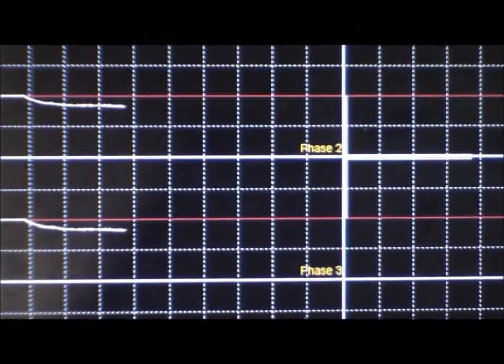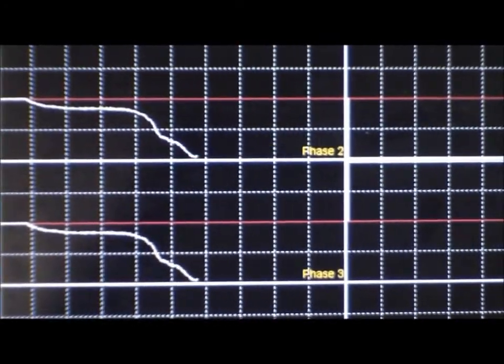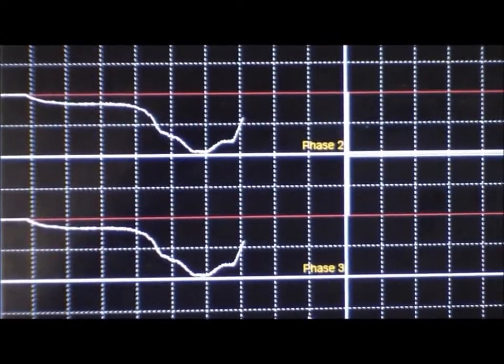This is the data collected while scanning a 50% blockage calibration piece. You can see the signal dropping as the scanner goes over the magnetite.